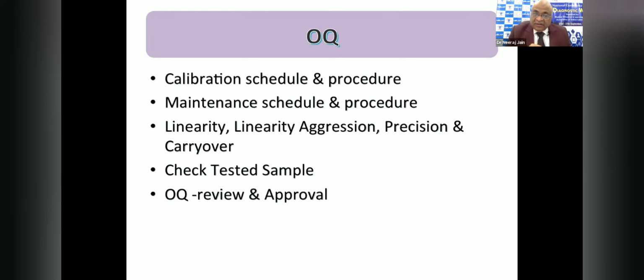Then after calibration, you are running controls, if required, of all three levels: low, normal and high. In routine biochemistry, low, normal and high level. When these control results are within accepted limits, you are checking with already tested samples. If you are getting comparable results, then you say, okay, I have checked everything, this machine is okay. Now we can use it for untested samples. The machine is ready to be used in the laboratory for untested samples which you receive as routine. So this is operational qualification.